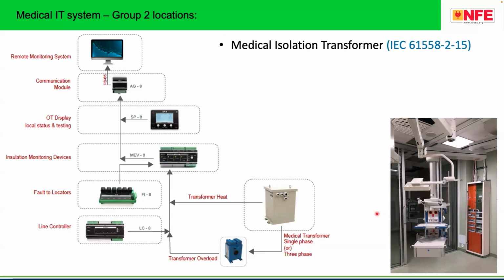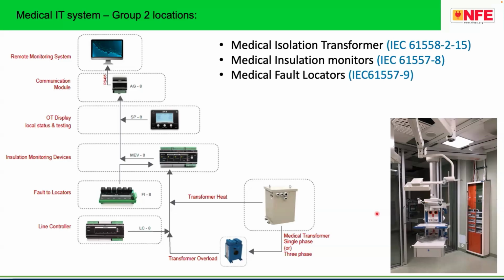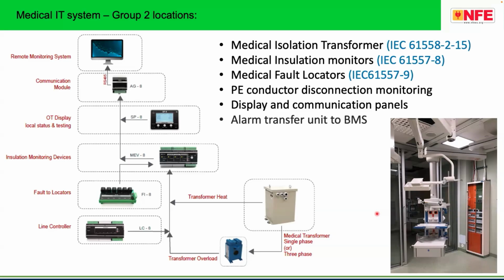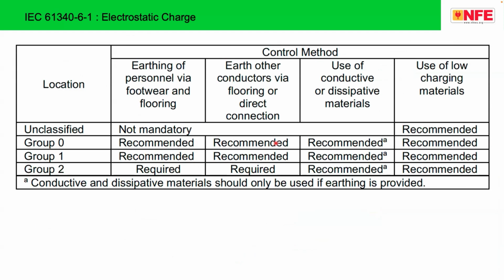Medical IT system consists of a medical isolation transformer as per this particular standard, a medical insulation monitoring system as per 61557-8, a medical fault locator 61557-9, and PE conductor disconnection monitoring, because one of the biggest challenges in India is that there is sometimes no earth wire. Then there are monitor display and communication panels, the alarm transfer unit, and transfer to BMS. So basically, this is an automated system which tells you that in a Group 2 location, even if there is a faulty equipment, the system need not trip. The power supply can continue and the patient is in a safer situation. The medical IT system in Group 2 locations is a mandatory requirement. Supplementary equipotential bonding in Group 1 and Group 2 locations is a mandatory requirement.